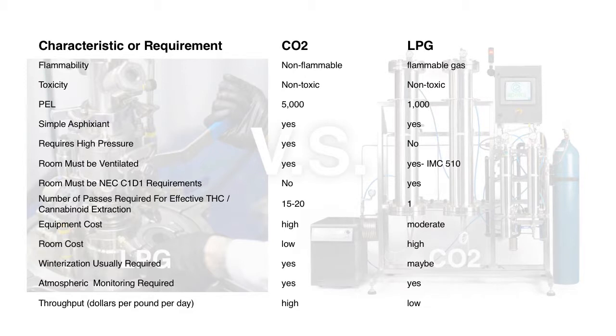We do need to monitor the atmosphere. For CO2, it would be a carbon dioxide monitor operating continuously, and for LPG, a flammability monitor operating continuously. Then the throughput, and when I say throughput, I mean dollars per pound per day, meaning the dollars invested in the amount of material you could process, essentially your speed. It's higher for CO2 and lower for LPG, but you have to look at the totality of these comparisons to decide what product your facility wants to make and how you want to make it.